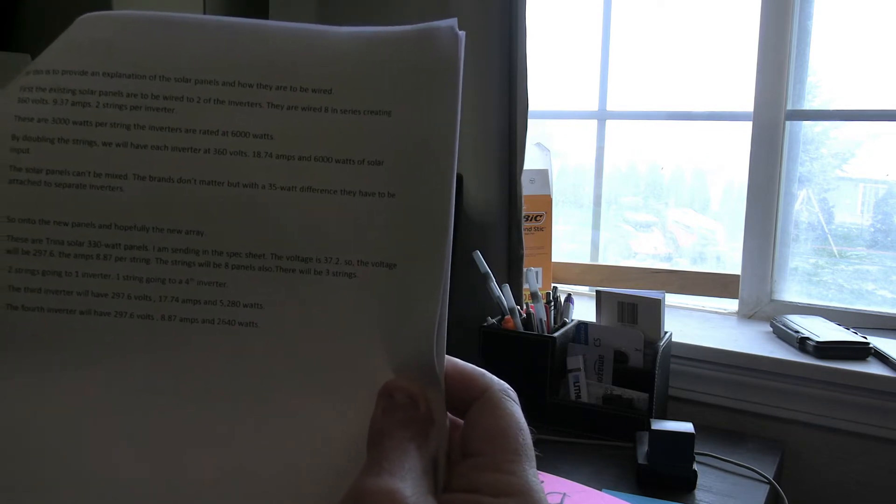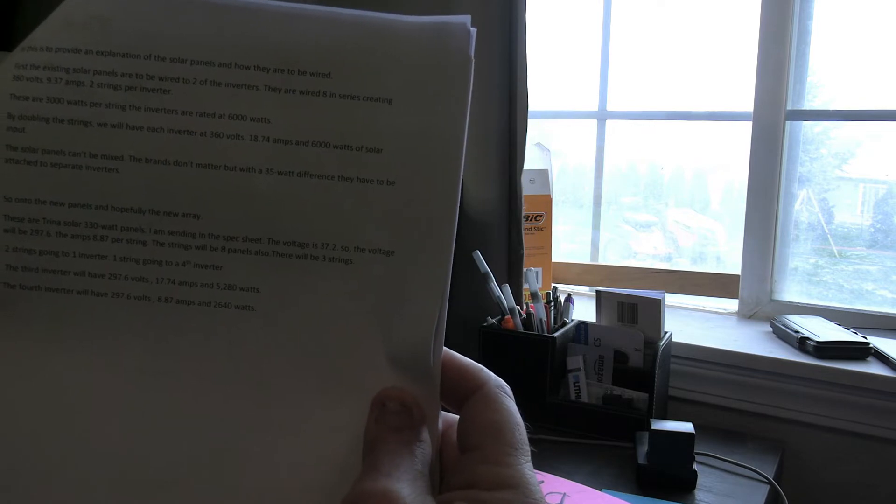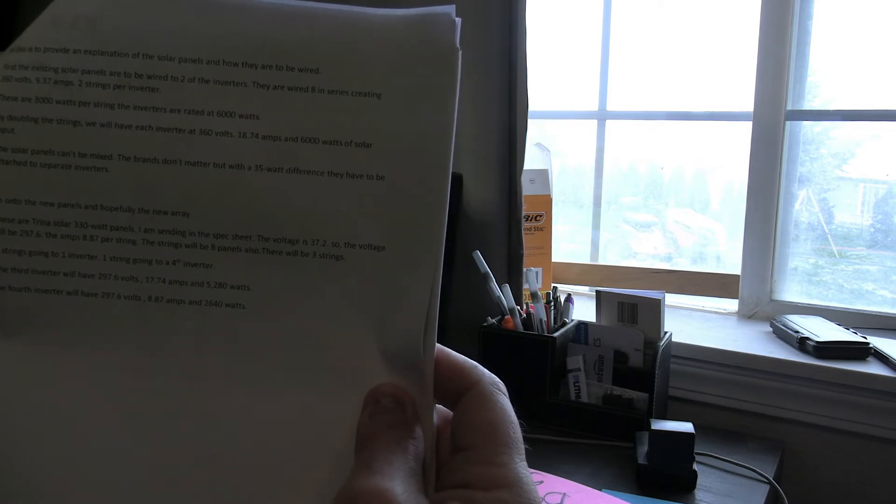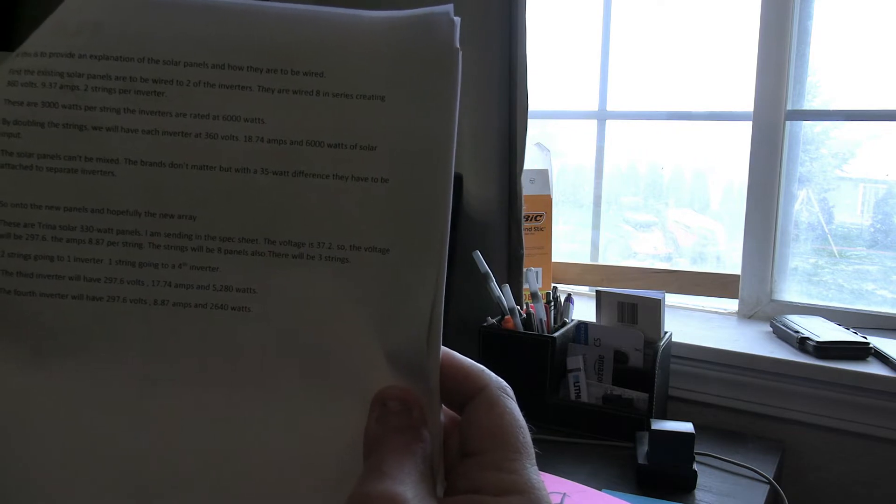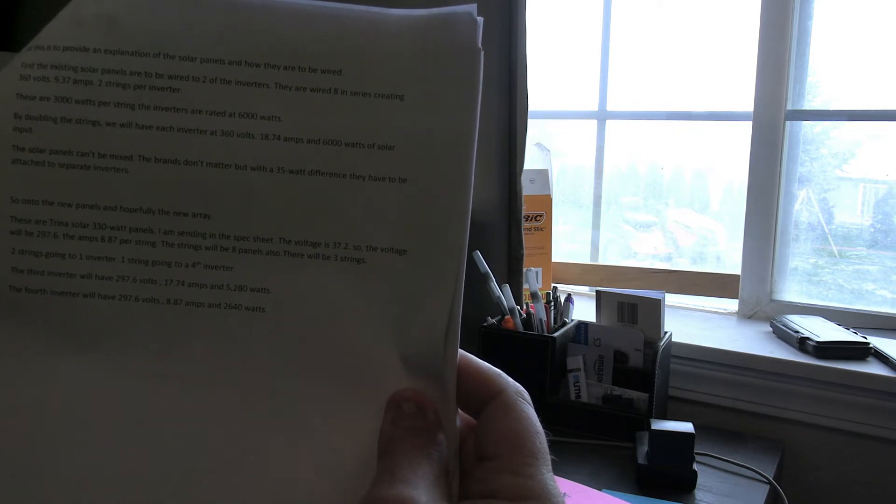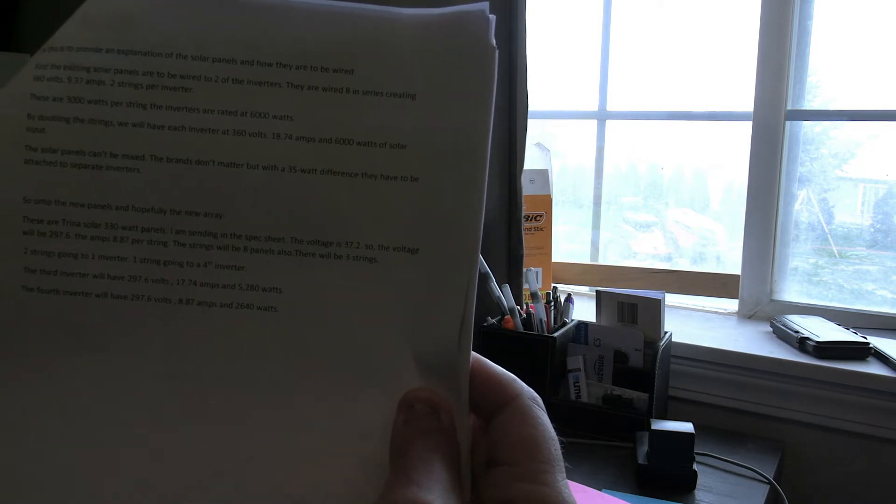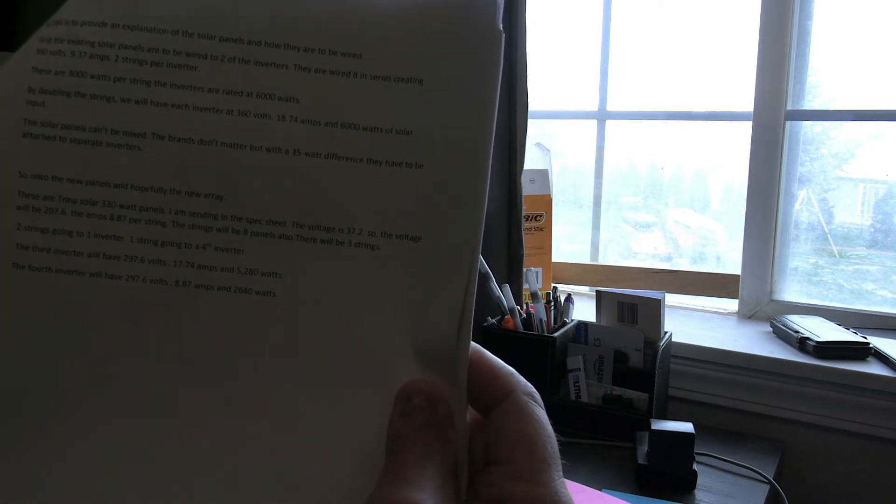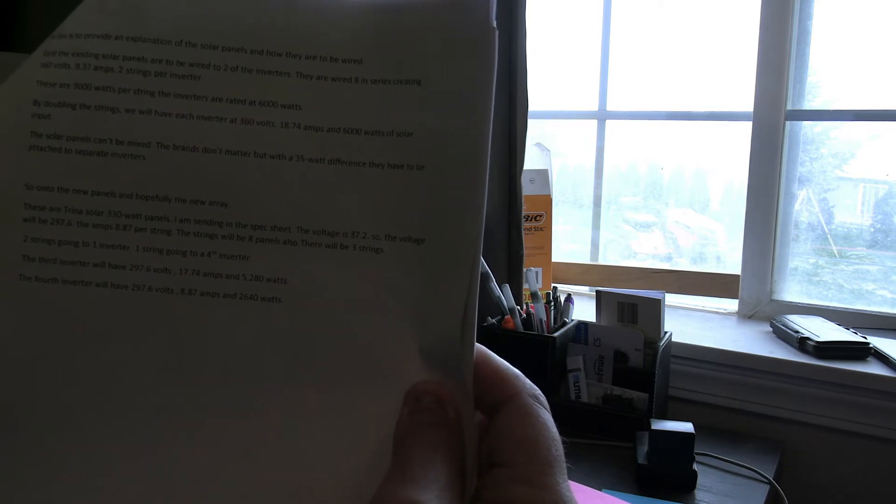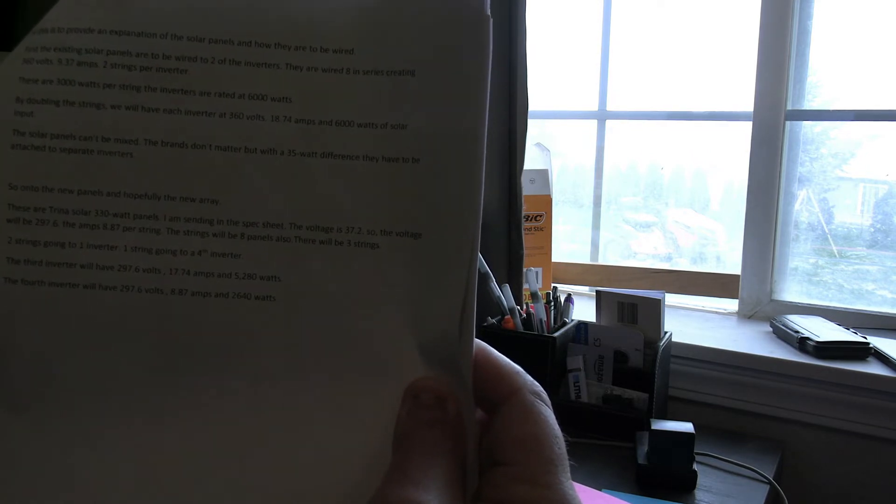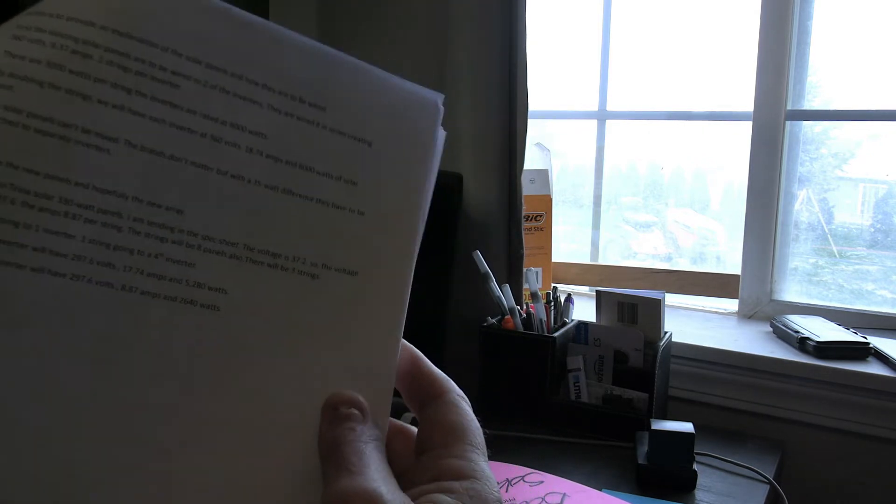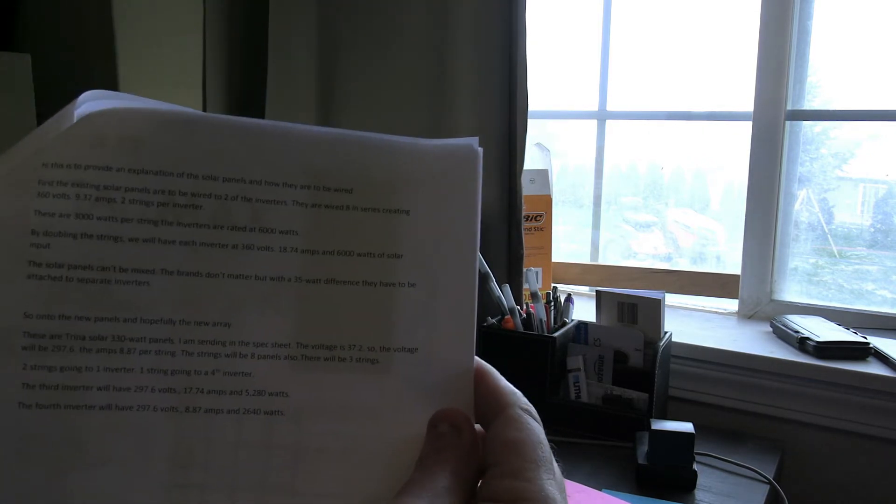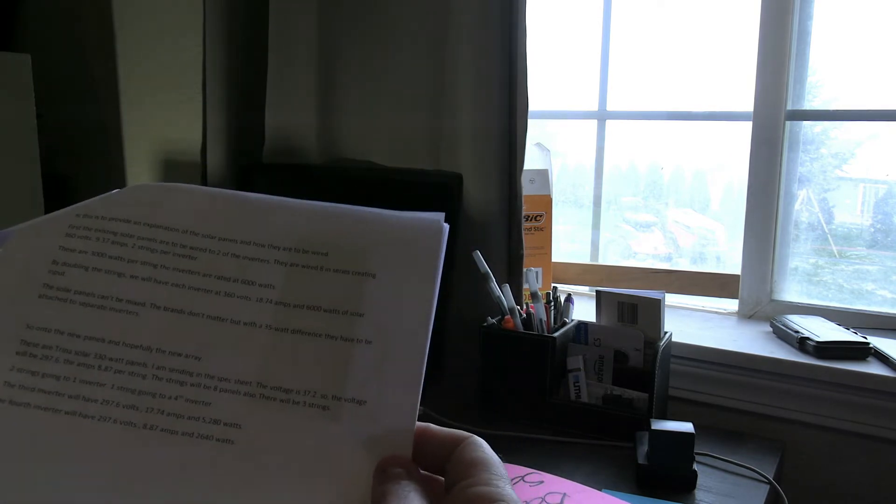There will be three strings, two strings going to one inverter, one string going to the fourth inverter. The third inverter will have 297.6 volts, 17.74 amps and 5,280 watts. The fourth inverter will have 297.6 volts, 8.87 amps and 2,640 watts. This is what I had to provide them in order for them to approve my plan.